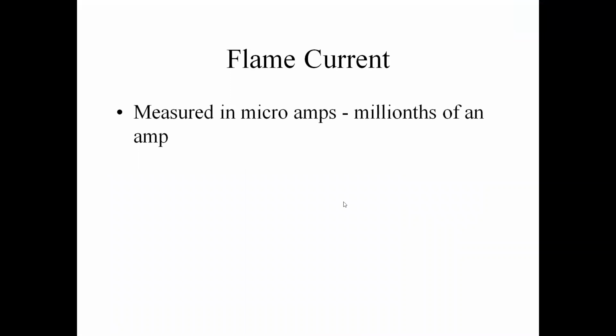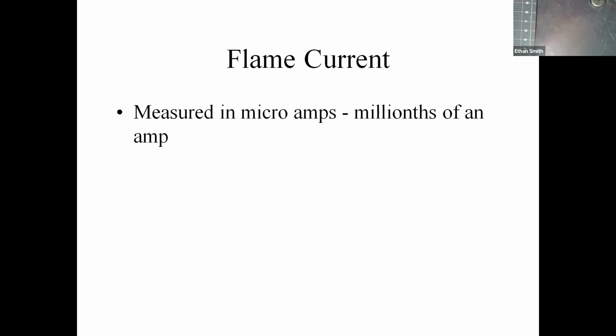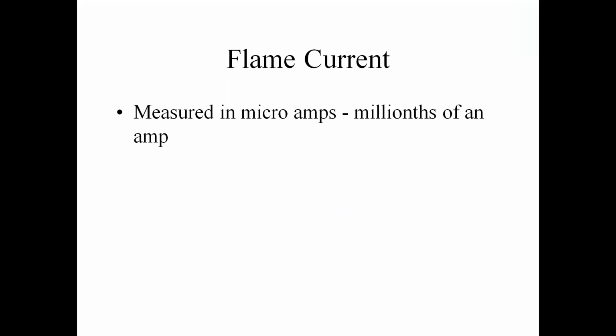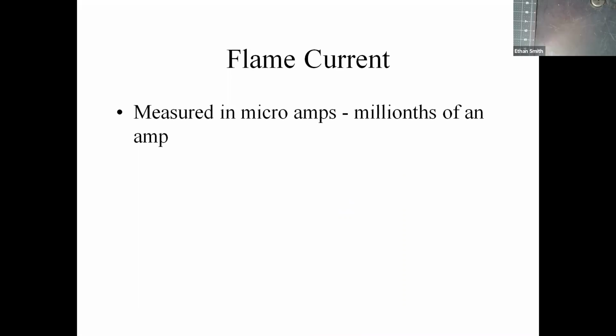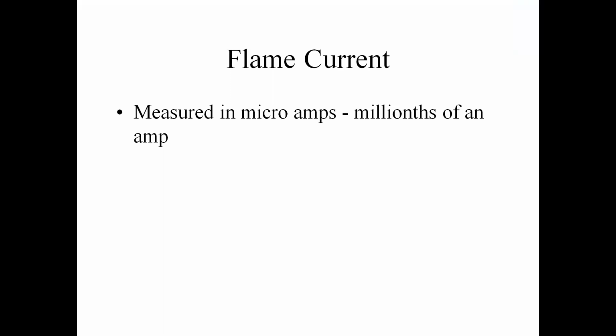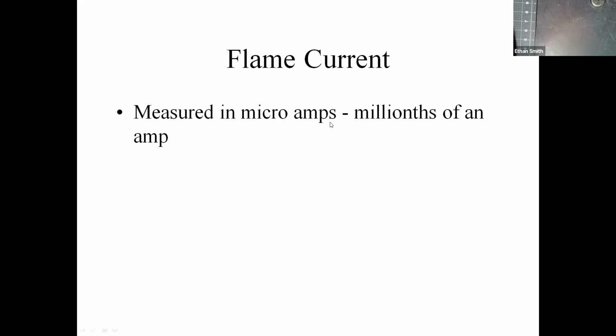Okay, so this is measured in microamps. Yes, sir. You can't be shocked if you touch the flames, right? It's just super low current. Well, you'll burn yourself before you shock yourself. While they are conductive, they're very poor conductors because we're actually measuring millionths of an amp through those flames. Now, if you hold on to the flame sensor, it might light up your life a little bit. Yeah, it's cool that the flames do carry a little bit of the charge, though. Yeah, but we're talking millionths of an amp. Okay, so it's not enough to damage you, but it will hurt if you hold on to that flame sensor and ground out.